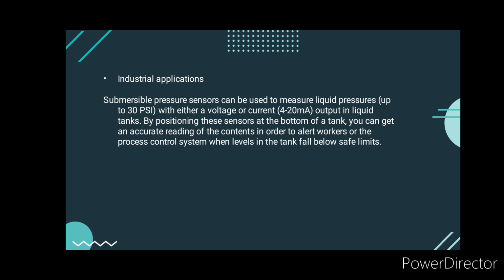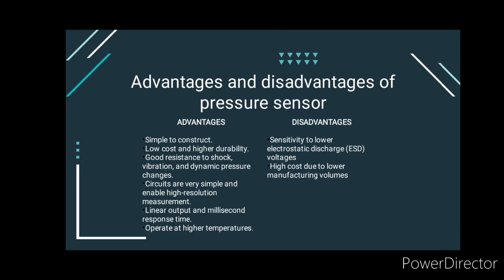Industrial applications. So, submersible pressure sensors can be used to measure liquid pressures up to 30 psi, with either a voltage or a current 4 to 20 milliamperes output, in liquid tanks. By positioning these sensors at the bottom of the tank, you can get an accurate reading of contents in order to alert workers or the process control system when levels in the tank fall below safe limits.